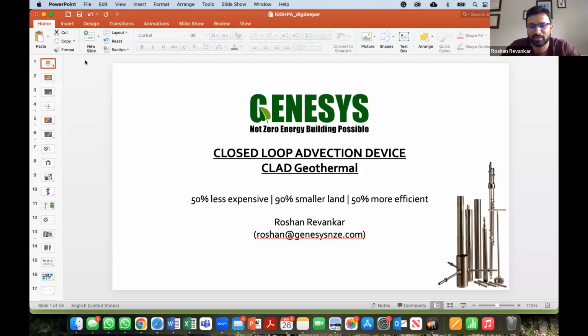Absolutely. I think Steve hit the nail on the head. The design just so happens to be that we can use propylene glycol. It's not something that you would need, as long as it's all below the frost line. It's more of a liability, and engineers like to add propylene glycol to the system. So in this case, you can add it, it's not always needed. Again, if you think about it, the way we've sized these is with propylene glycol.